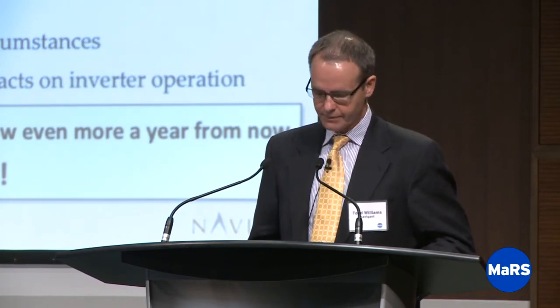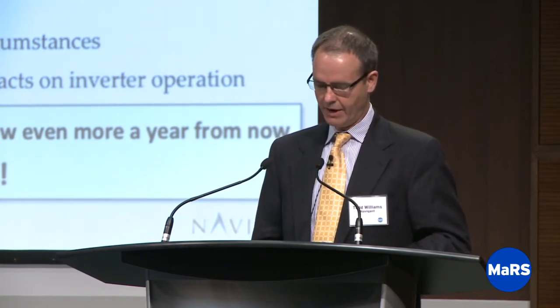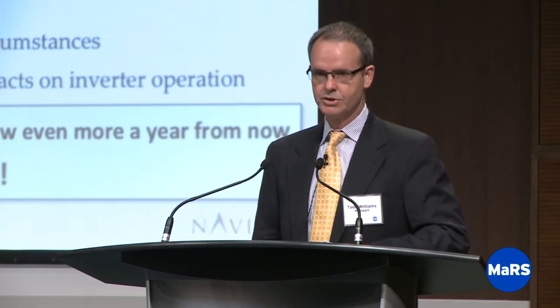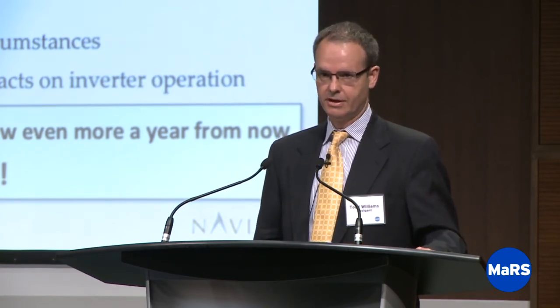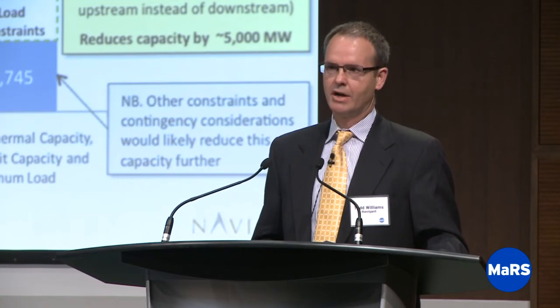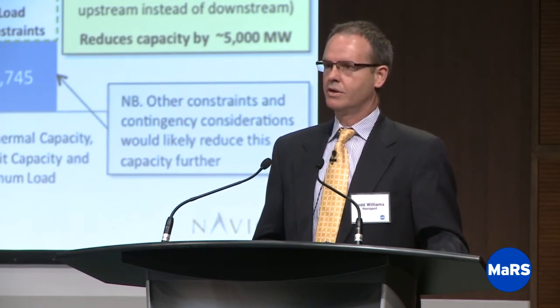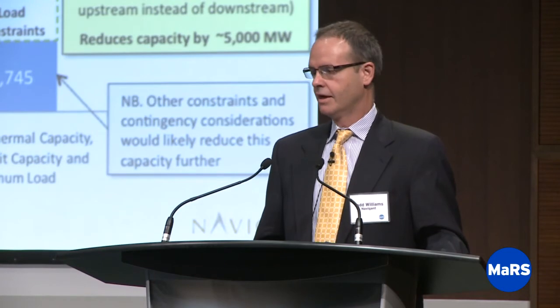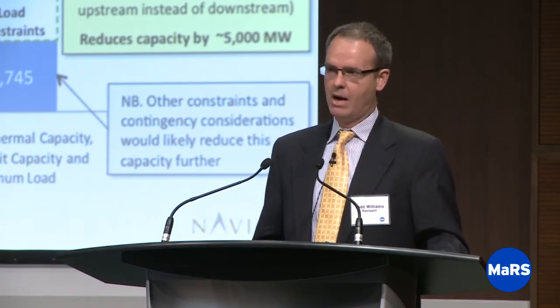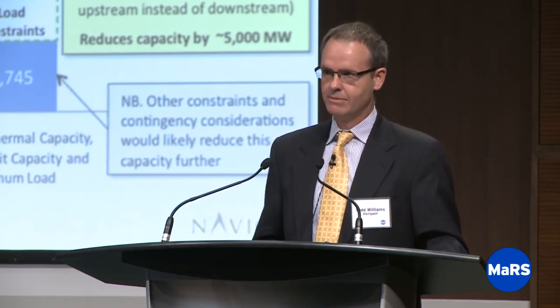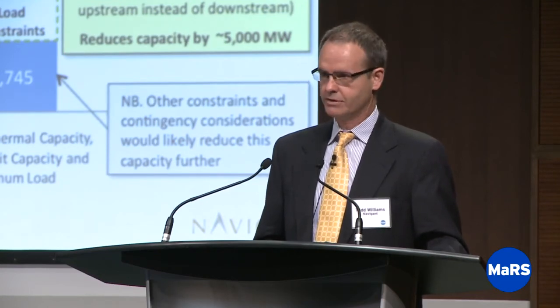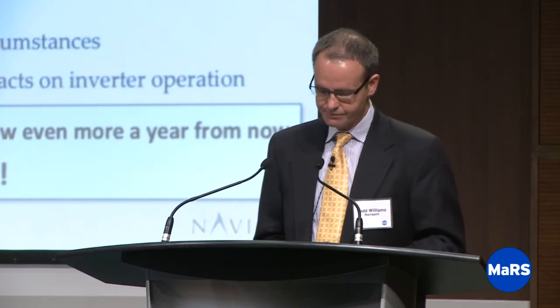Hydro One and CanSIA have established a working group and retained a consultant to explore the contribution of PV to short circuit levels. If you recall this chart, that's where we lost about 5,000 megawatts of capacity. There's a big question about whether an inverter contributes, say, one times its power rating, or 1.1 or 1.2 times its power rating, to short circuit levels, and there's discussion underway to get a better understanding of that.